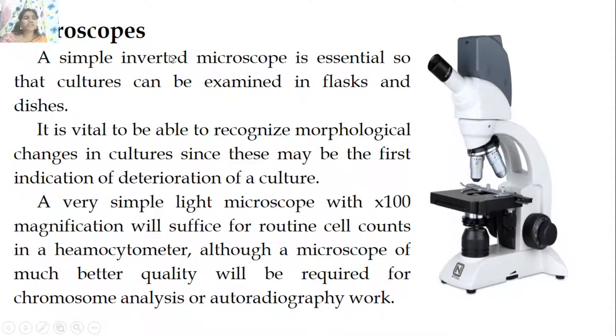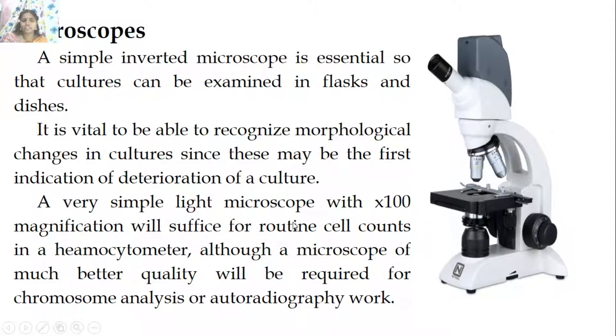A simple inverted microscope is essential so that cultures can be examined in flasks and dishes. It is vital to recognize morphological changes in the culture after growth, as this may be the first indication of deterioration. A simple light microscope with 100x magnification is sufficient for routine cell counts in a hemocytometer, though better quality microscopes are required for chromosome analysis and autoradiography.